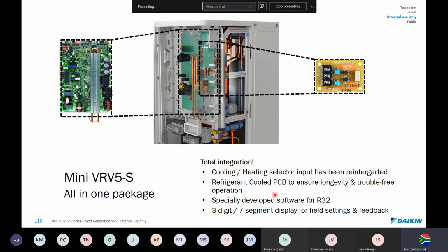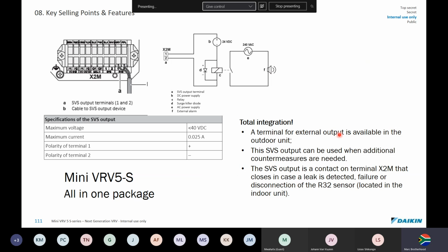The refrigerant cooled PCB is also obviously there to ensure longevity and trouble-free operation. So there's all the liquid refrigerant running through, cooling down the thyristors and IGBT module. Obviously, we've designed specific software to handle R32, and it's got the 3-digit 7-segment display for field settings.